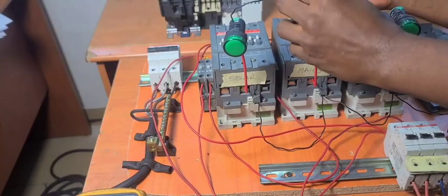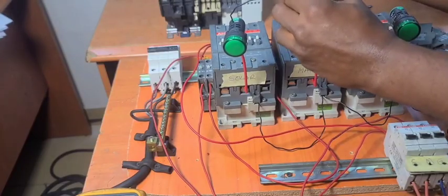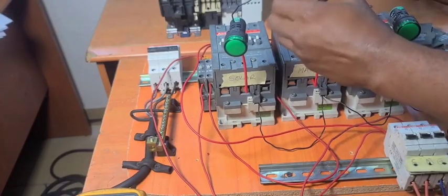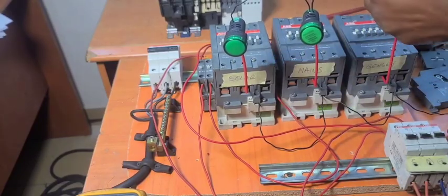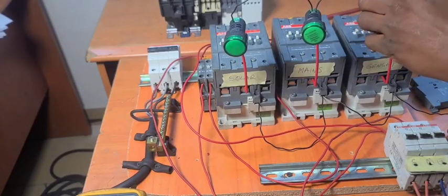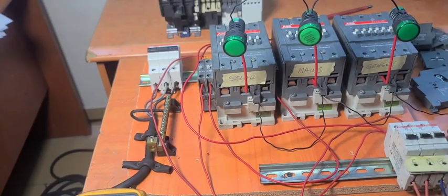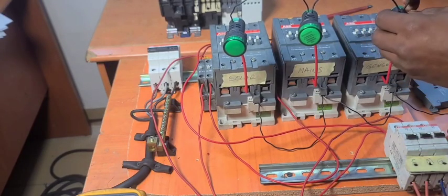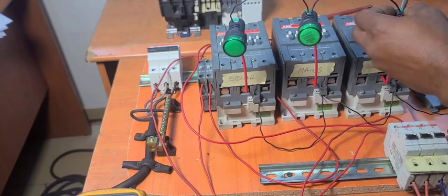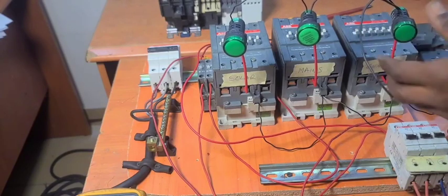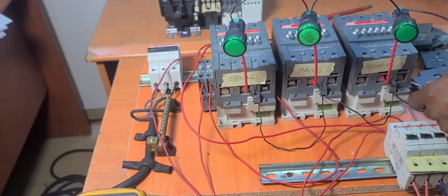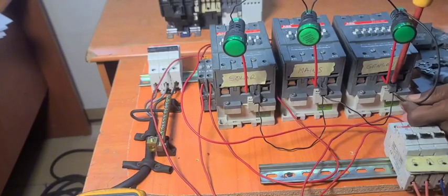So you're just going to go from the solar indicator onto the mains indicator, and from mains indicator it is going to go to the generator indicator. And when that is done, we are going to wire this neutral down to A2 on the generator contactor.